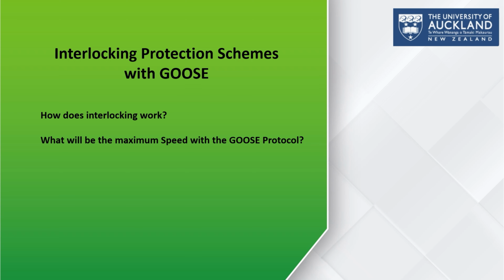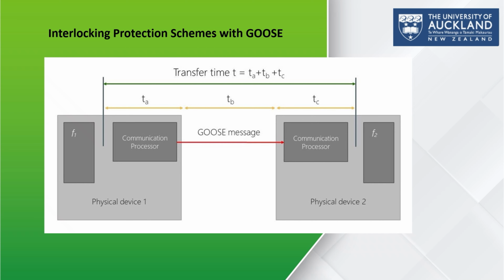In addition to the native security features of interlocking schemes, the operational reliability can be further enhanced by inherent supervision of GOOSE messages. When a blocking circuit is broken, unnecessary tripping is avoided as the blocking is not being issued. So instead of rendering the protection inoperative, in such a case, GOOSE inherent supervision generates an alert to initiate the maintenance repair process and react as quickly as possible. This supervision function can also be utilized to adapt to application requirements. Depending on the object-to-object protection, one function must often be prioritized over another. For instance, it may be necessary to sacrifice some operational speed in order to achieve selectivity, or vice versa. Such adjustment can be easily made in the configuration of the GOOSE service in order to obtain the best protection possible.